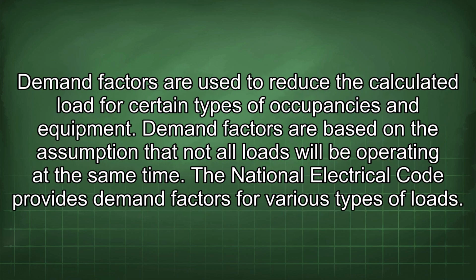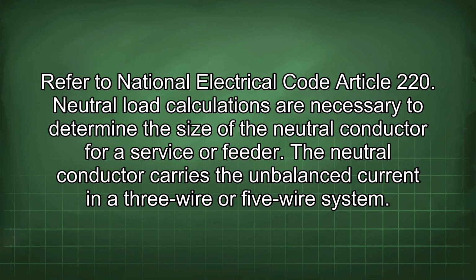Demand factors are used to reduce the calculated load for certain types of occupancies and equipment. Demand factors are based on the assumption that not all loads will be operating at the same time. The National Electrical Code provides demand factors for various types of loads. Refer to National Electrical Code Article 220.